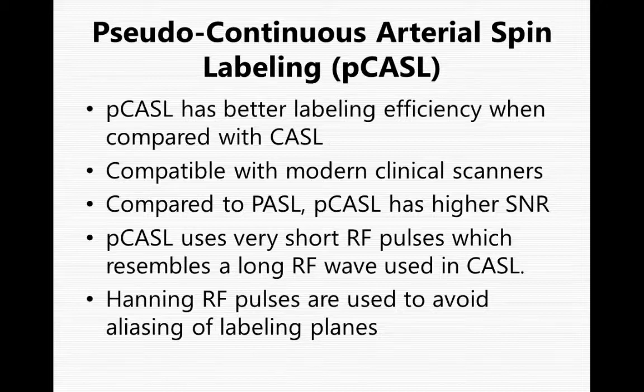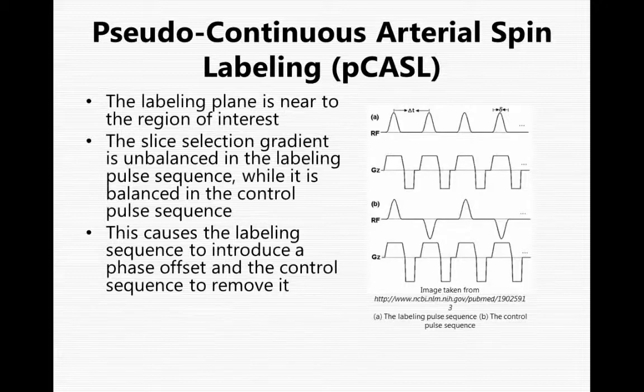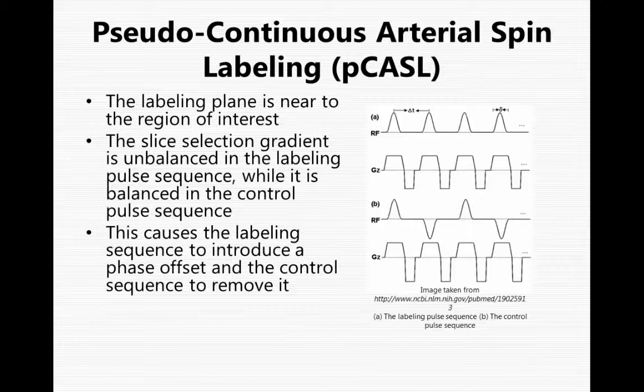Hanning RF pulses instead of rectangular RF pulses are used to avoid aliasing of the labeling planes. In PCASL, the labeling plane is near to the region of interest. On the right side, you can see the two labeling sequences used in PCASL. The sequence marked with A is the labeling pulse sequence, while the sequence marked with B is the control pulse sequence. The slice selection gradient is unbalanced in the labeling pulse sequence, while it is balanced in the control pulse sequence.